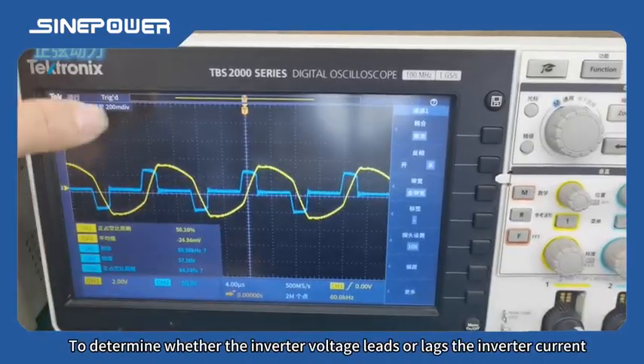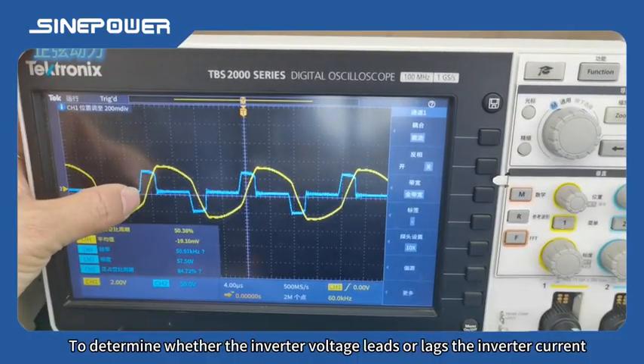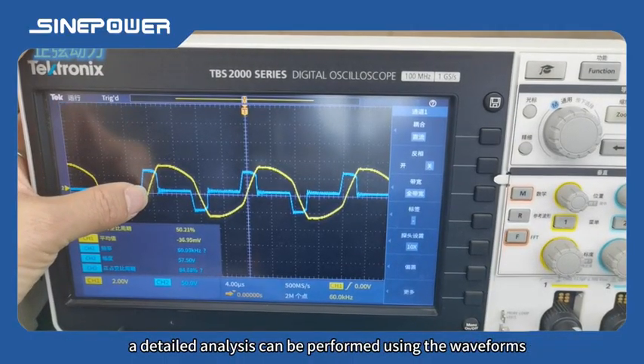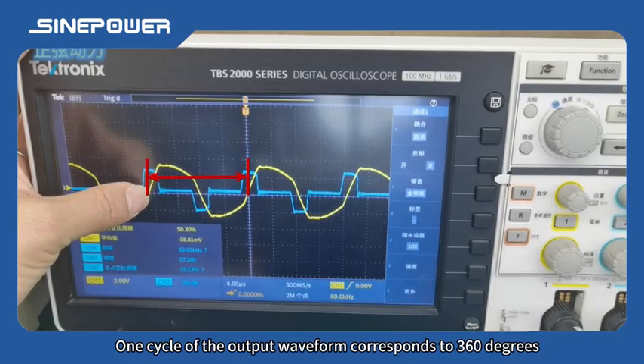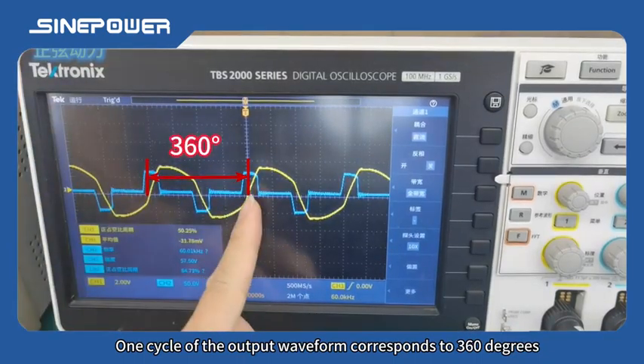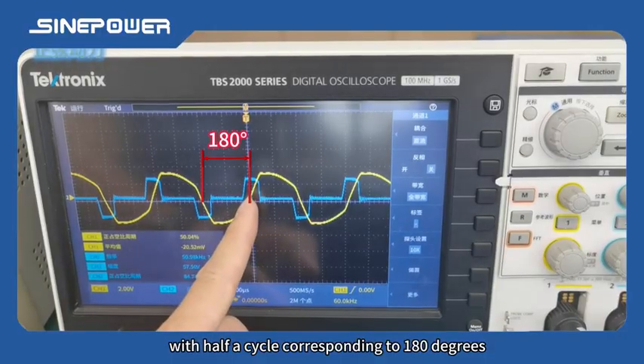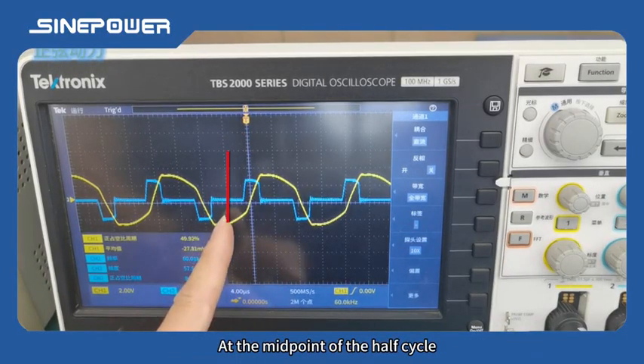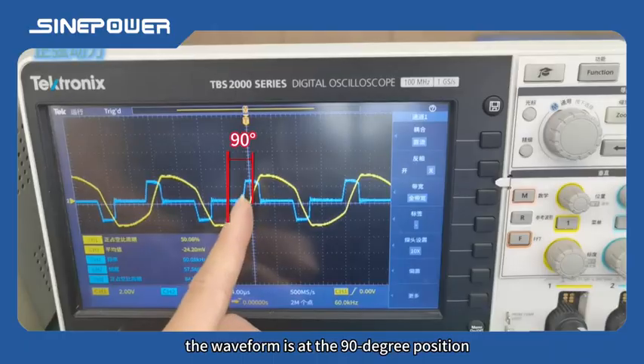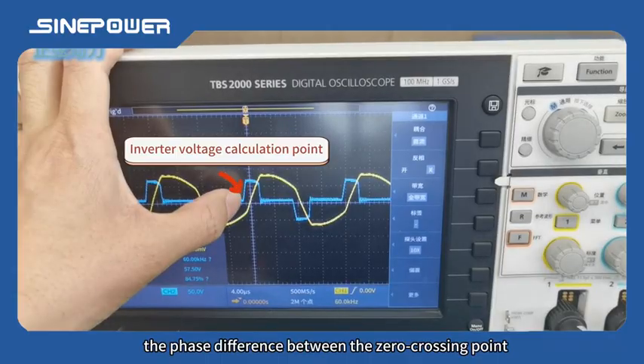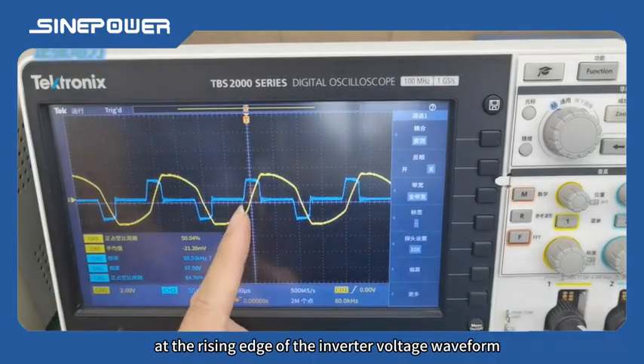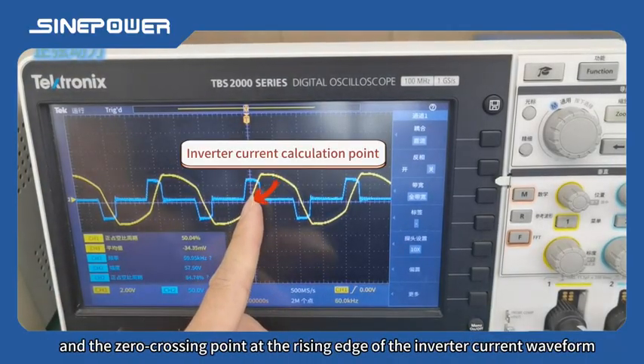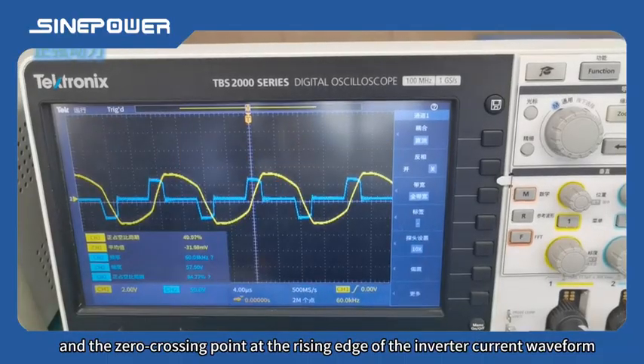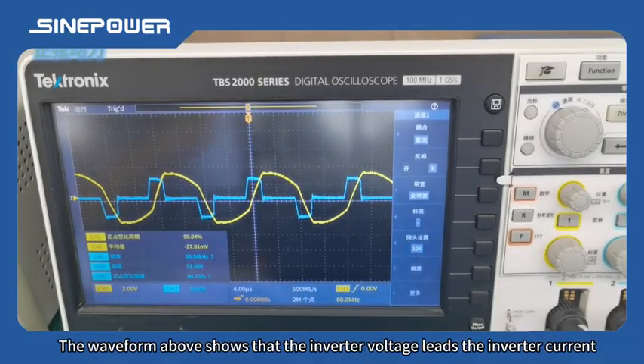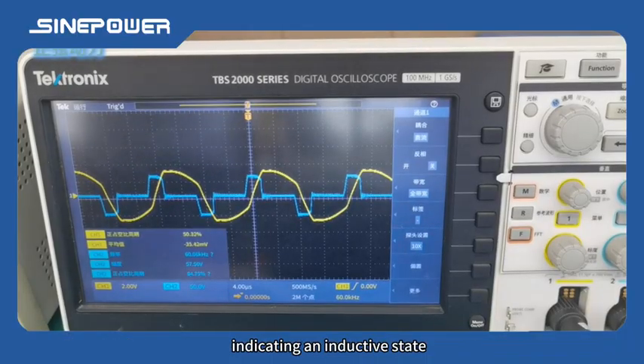To determine whether the inverter voltage leads or lags the inverter current, a detailed analysis can be performed using the waveforms. One cycle of the output waveform corresponds to 360 degrees, with half a cycle corresponding to 180 degrees. At the midpoint of the half cycle, the waveform is at the 90-degree position. The actual phase calculation is based on the phase difference between the zero crossing point at the rising edge of the inverter voltage waveform and the zero crossing point at the rising edge of the inverter current waveform. The waveform above shows that the inverter voltage leads the inverter current, indicating an inductive state.